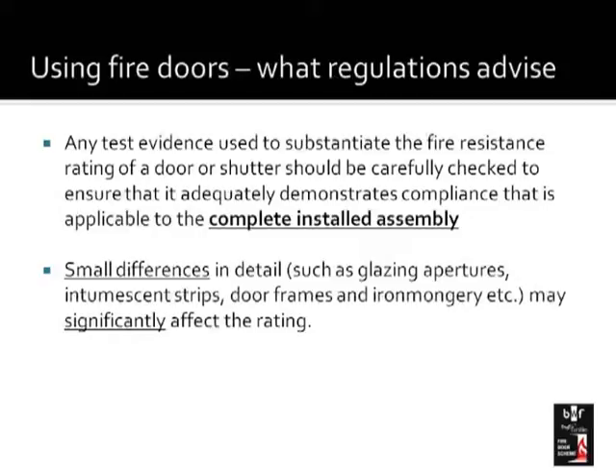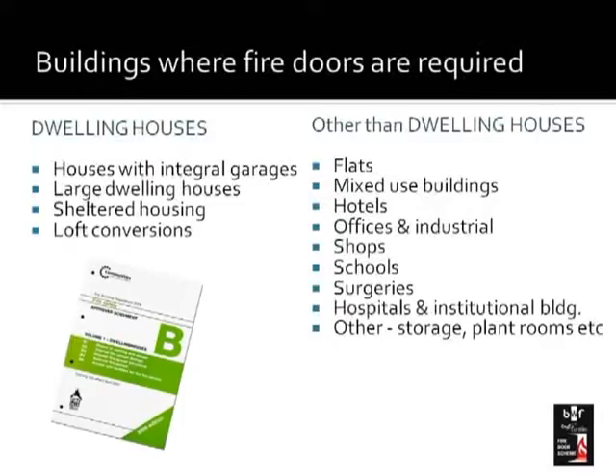If you don't fit the correct intumescent seals, the correct door frames, or the correct ironmongery, you can significantly affect the rating of the fire door — and that's particularly relevant to glazed apertures. Under the building regulations, fire doors are required for either dwelling houses or other types of buildings. In the case of dwelling houses, fire doors are required in houses with an integral garage, in large dwelling houses, or in loft conversions. The same applies to other types of buildings — flats, mixed-use buildings, hotels, shops, schools, and all other types of public buildings. So most buildings in the UK need to have fire doors.